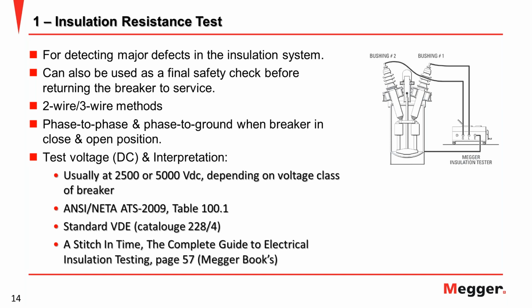So actually there are two methods for testing insulation resistance, 2-wire or 3-wire method. The 2-wire is the common test. You just need two cables. We inject a DC high voltage into the object to be tested, and then you measure the leakage current. And the test equipment can calculate, based on Ohm's law, the resistance value in megaohms. Usually this test uses 2500 volts or 5 kV DC, depending on the class of the breaker.